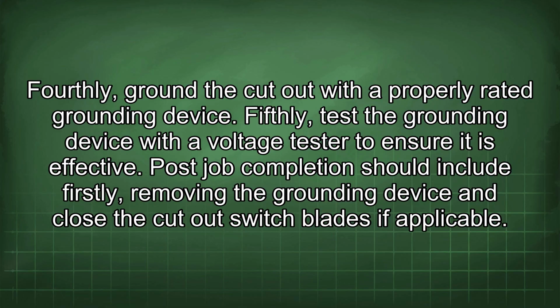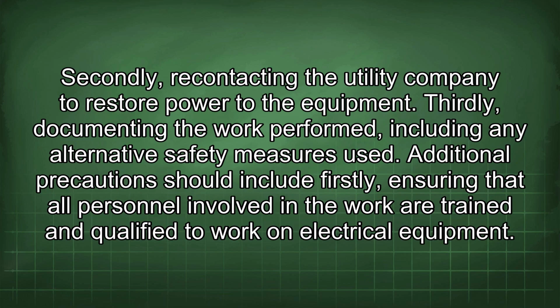Post-job completion should include, firstly, removing the grounding device and closing the cutout switch blades if applicable. Secondly, recontacting the utility company to restore power to the equipment. Thirdly, documenting the work performed, including any alternative safety measures used.